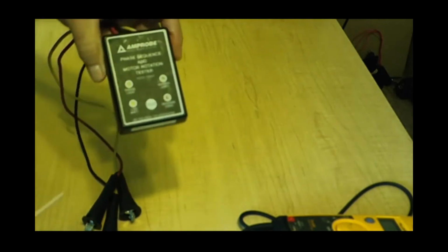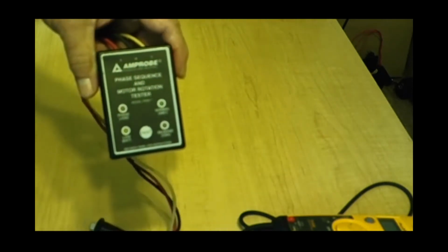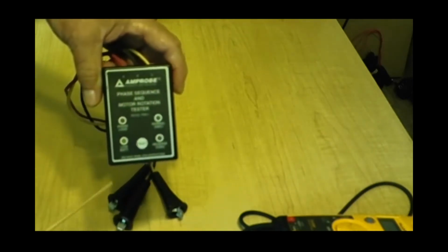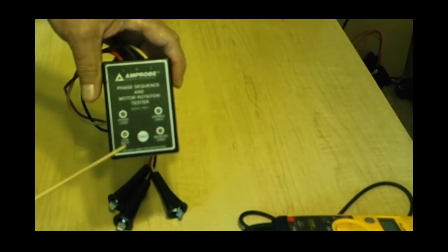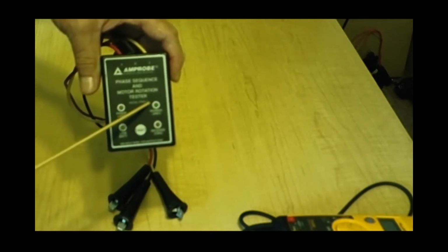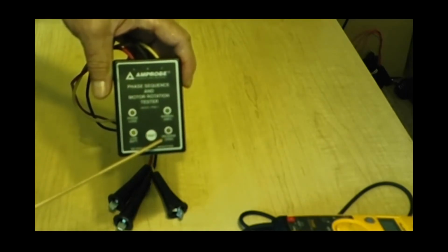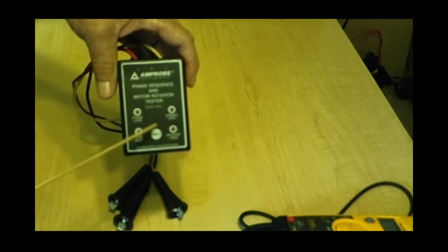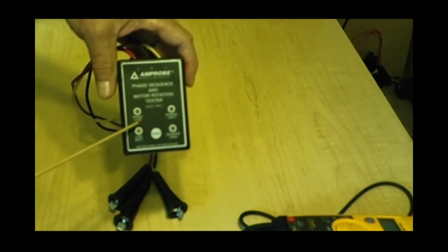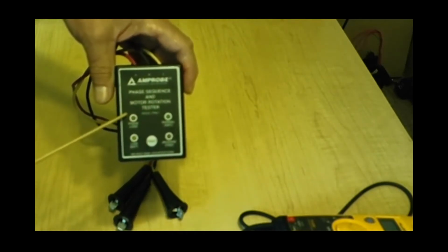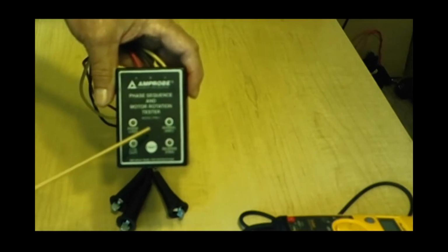This meter right here has been used in industry for a long time. It is a rotation tester. It tests rotation of magnetic fields in three-phase circuits. It tells me right there if you have a normal ABC rotation, which is clockwise, or a counterclockwise rotation of CBA. It tells us if we lost a phase right there or a leg in the building. So very useful tools these are.